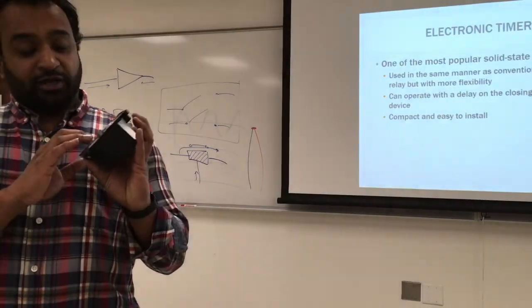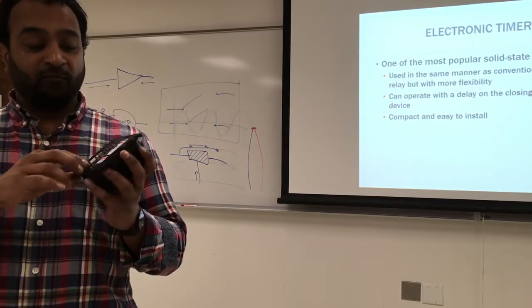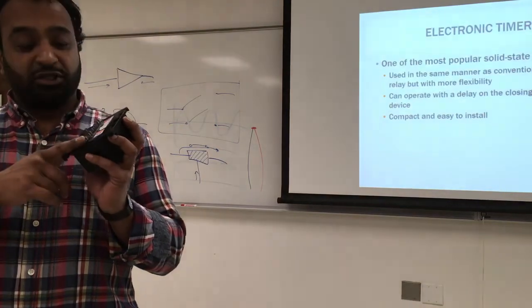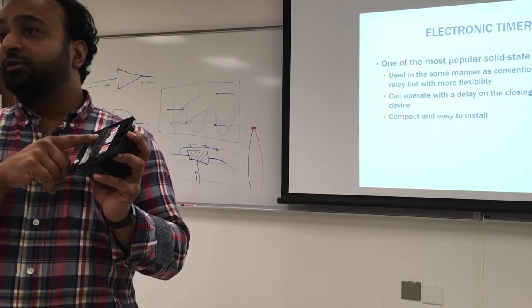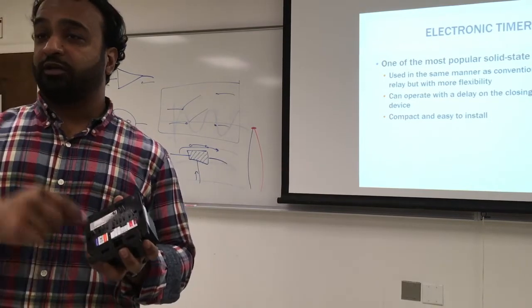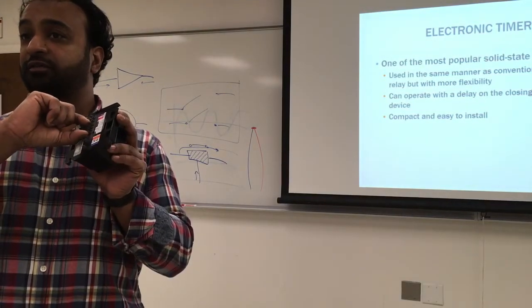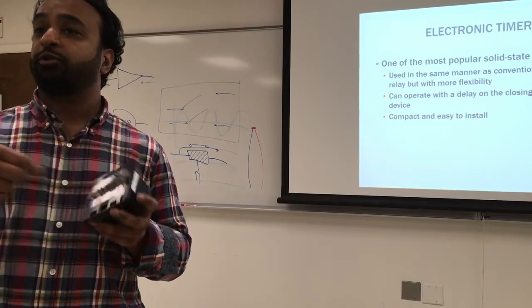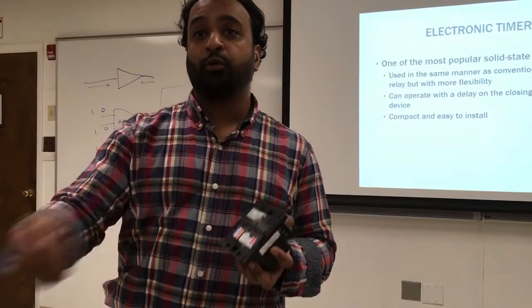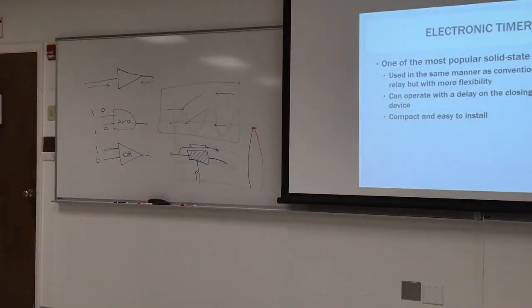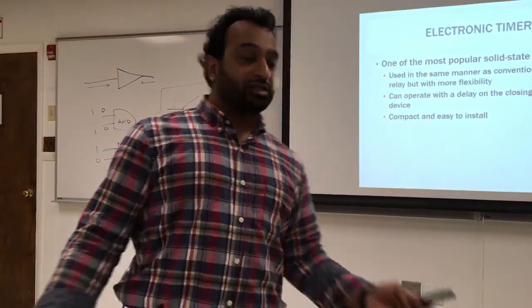Also, if you notice at the bottom here, they're trying to make you have very concise wiring. For all components, like ignition, motor, or valve, there's a neutral line here, so you don't have to run all the neutrals together in a bundle. You can go back to the control. These four neutral lines are connected together. One of them goes to the neutral from the power line, and the other subcomponents go into the control, which is very convenient. Before that, you had to bundle everything in one big wire nut, or put them in a bridge. So this is very convenient.